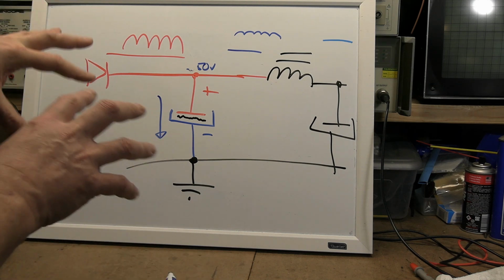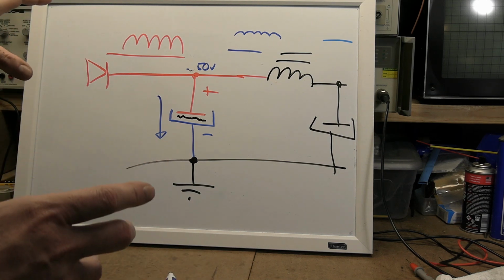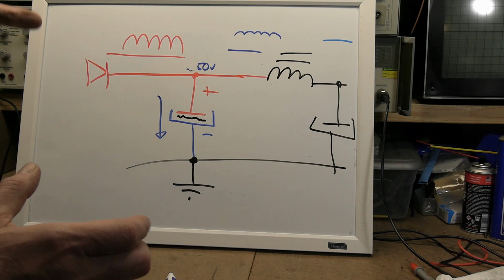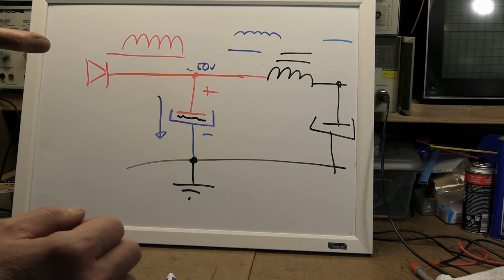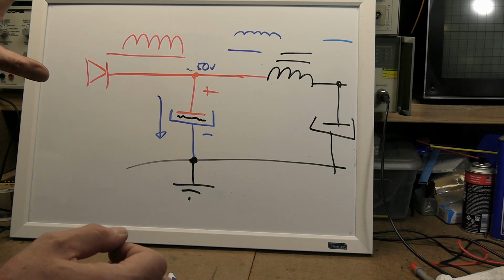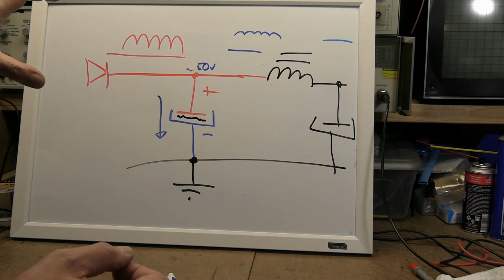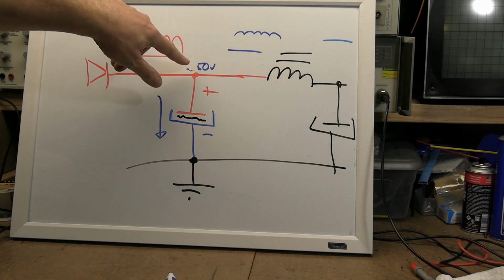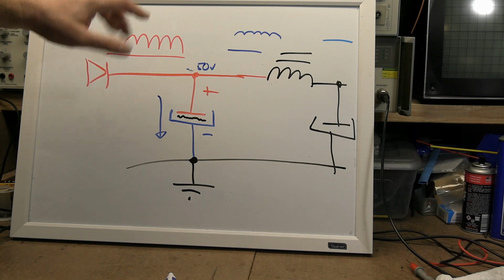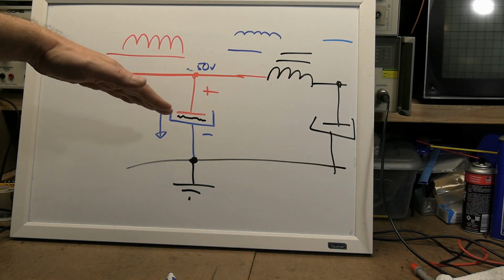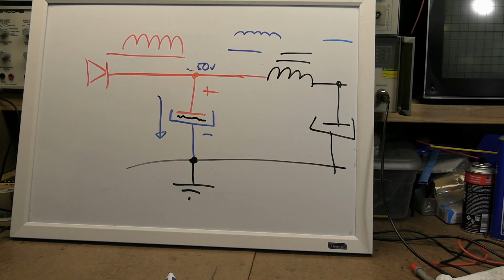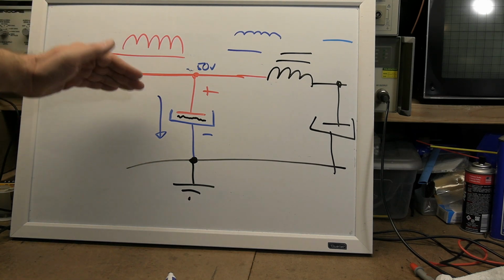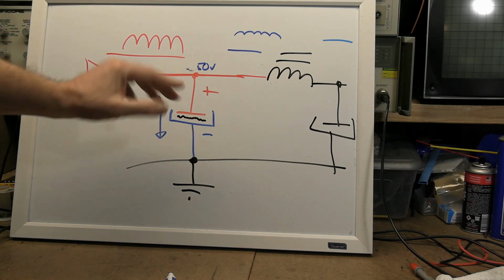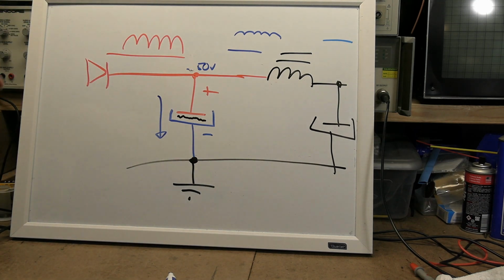But if at 50 volts, say we get 5 milliamps, we're going to want to slow down for a bit. And if it's capable of reforming, and maybe it's at 5 milliamps at 50 volts, watch it. After a minute, maybe it's down to 4 milliamps. A little bit longer, down to 3. And maybe after 10-15 minutes, it's below 1 milliamp. Then you turn this voltage up, maybe go to 75 volts. The leakage current will go up again. And you wait. And ideally, the leakage current drops down. So every time the leakage current drops down and levels out, you turn up the knob a little bit on your Variac if you have one.